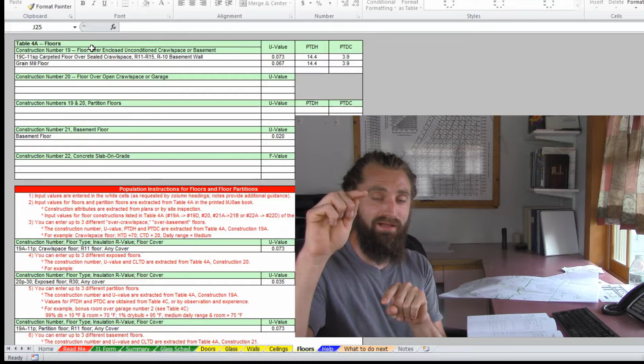We also had the grain mill floor, the original grain mill floor that was in that building from the 1800s. That's not going to be found in a program, so what I had to do is first determine the species of wood, then determine the average thickness of that wood, which was 2 inches. Then I could determine the slab R value, add to it the insulation value, and then take the inverse or reciprocal of it to give myself a U value for that grain mill floor.